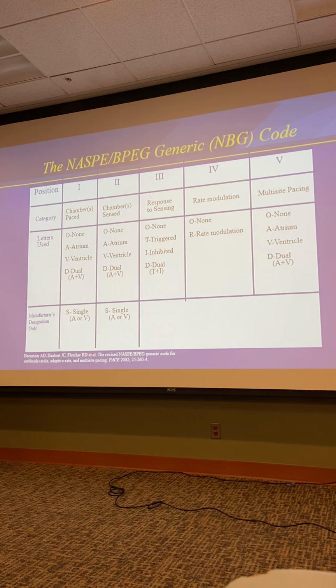The other thing that is less well known about applying a magnet is that when you put the magnet on a pacemaker, the rate that it paces at is a rate that cannot be programmed in. We can tell a pacemaker to go at 60, 65, 70, 75. We can't tell it to go at 62 and a half or something in between those fives. But when you apply a magnet, it goes at a rate that can't be programmed in, typically like 87 beats per minute. And that's how you know if you see a strip that it was either magnet application or ventricular pacing.